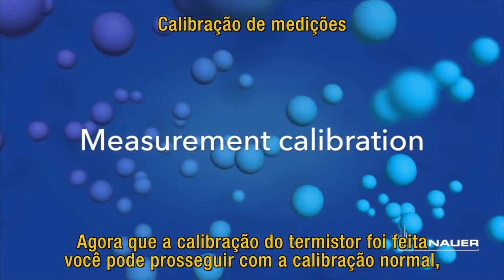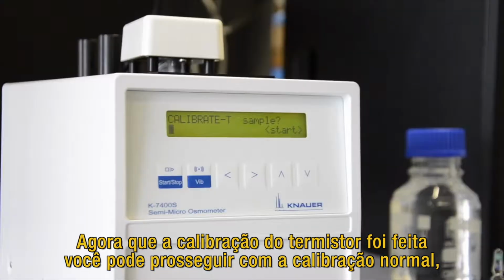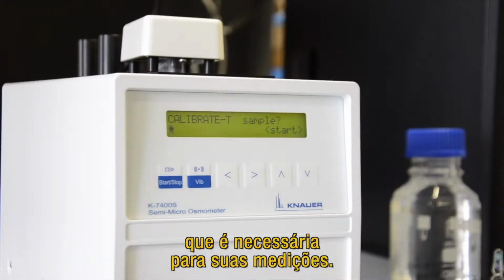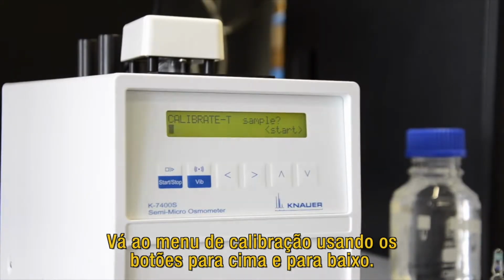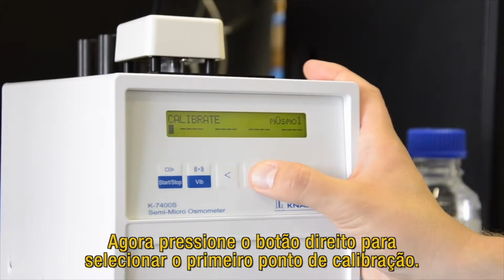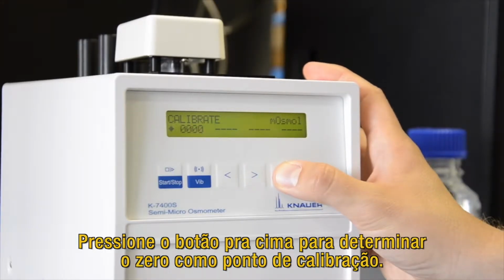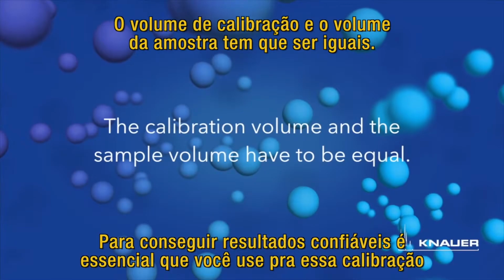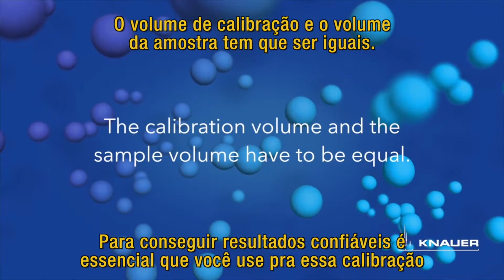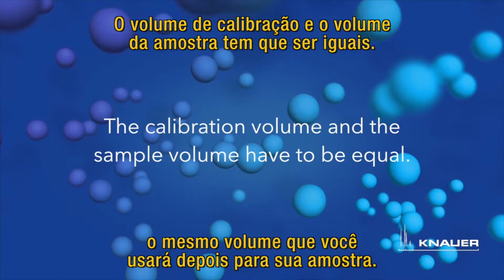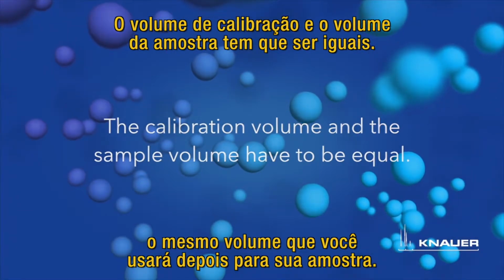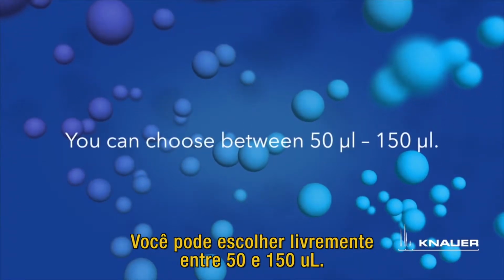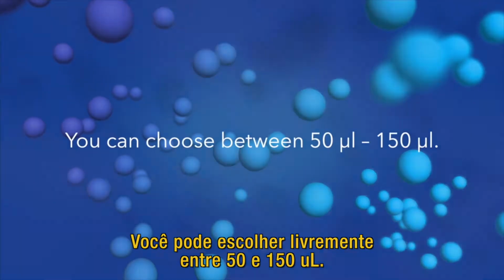Now that the calibration of the thermistor is done, you can proceed with the normal calibration which is needed for your measurements. Go to the Calibrate menu using the up and down buttons. Now press the right button to select the first calibration point. Press the up button to set the calibration point to 0. To get reliable results, it is essential that you use for this calibration the same volume that you are later using for your samples. You can choose freely between 50 and 150 microliters.